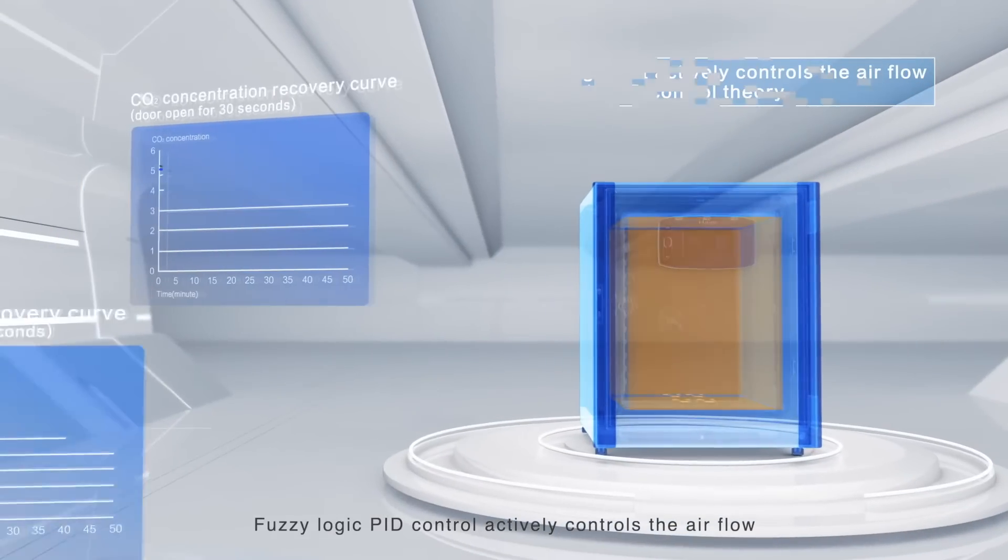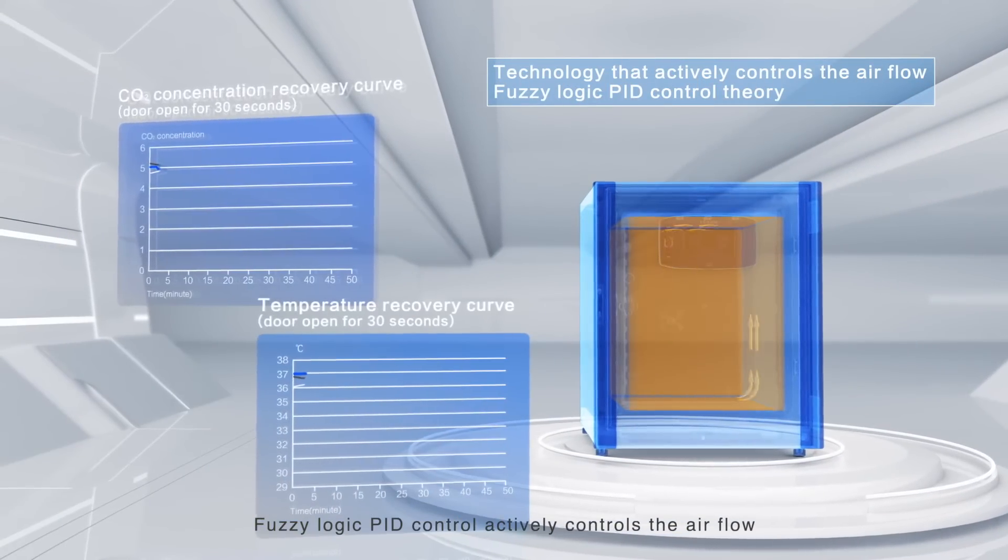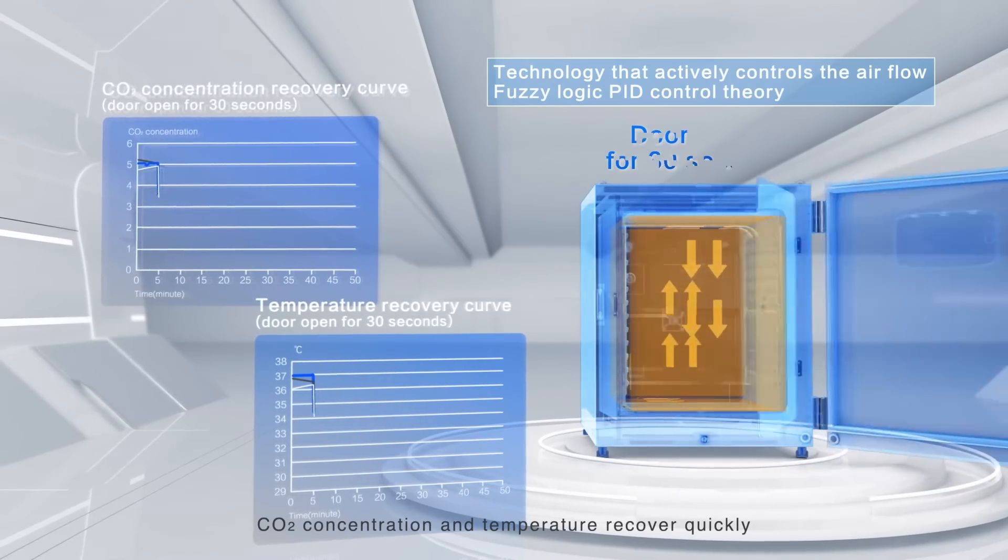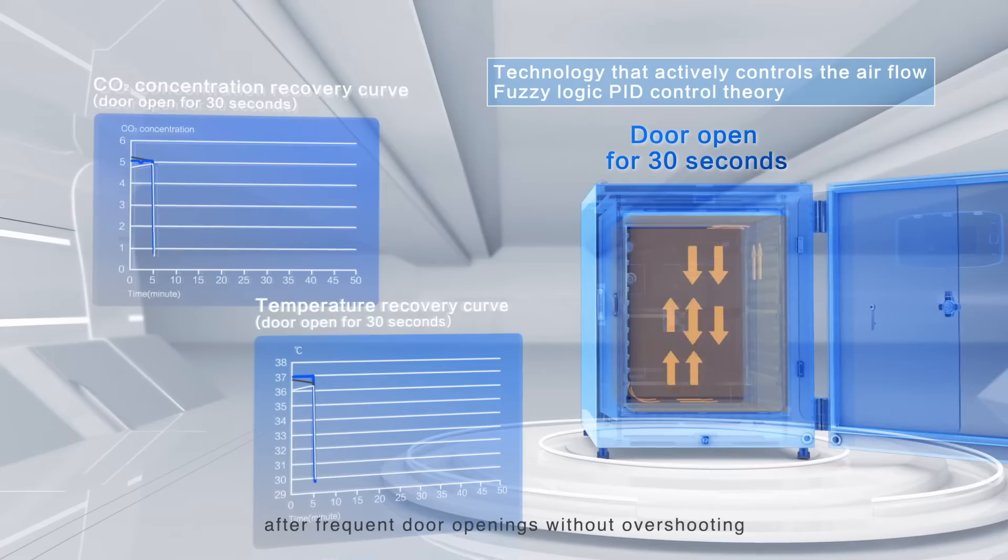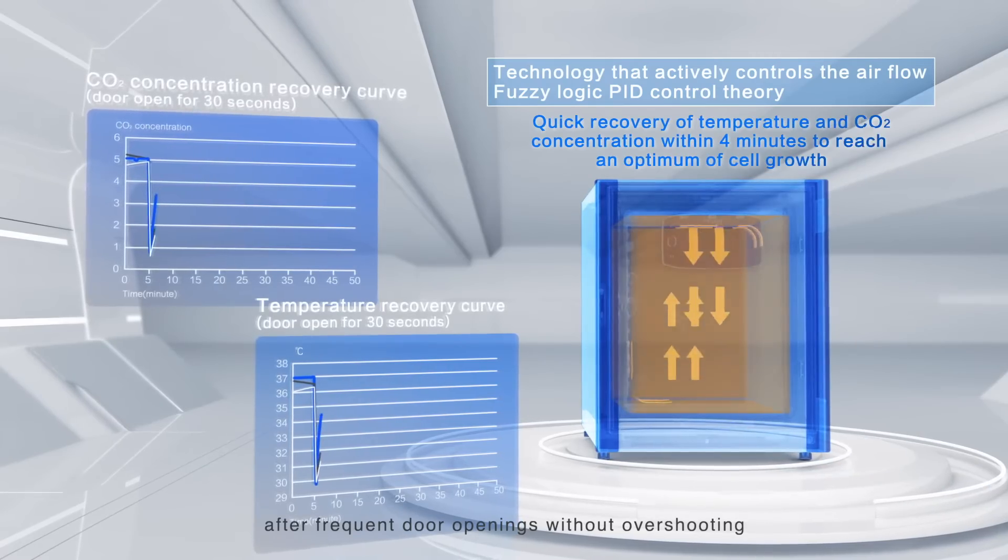Fuzzy Logic PID control actively controls the air flow. CO2 concentration and temperature recover quickly after frequent door openings without overshooting.